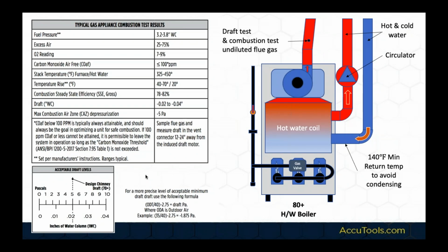The bottoms of them will rot out if you do not have the water split correct. So you really, really pay close attention on boilers to return air water temperature. Very, very important to make sure that we don't get condensing in places that we shouldn't be condensing on there.